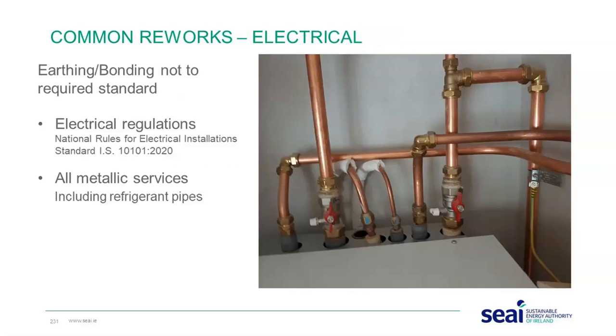Common reworks: electrical earthing and bonding. We can see from this image there's an earth brought to it, but the pipes aren't cross-bonded. What I would like to say is that all metallic surfaces need to be cross-bonded, including the refrigerant pipes. It's stated in I.S. 10101:2020. Just in case you're not aware, that's the newer version of ET 101.